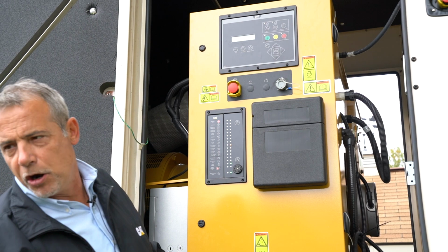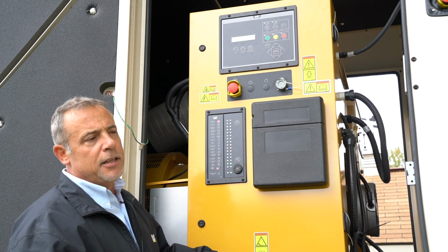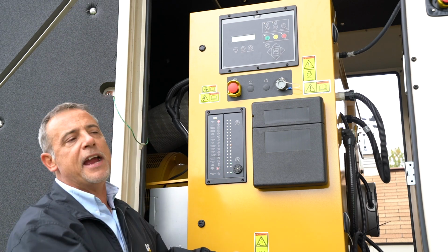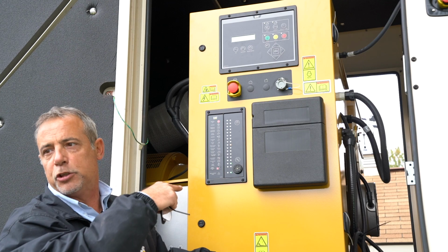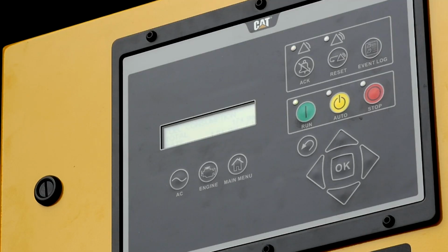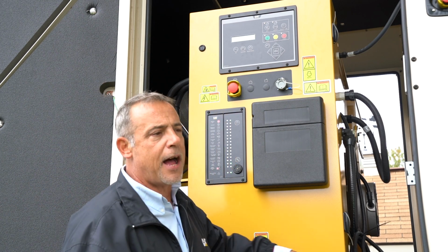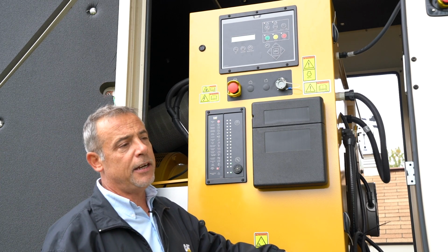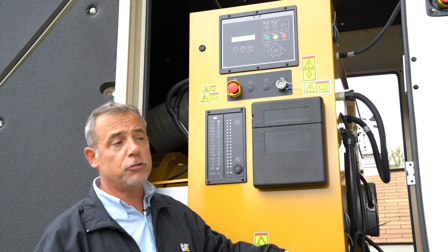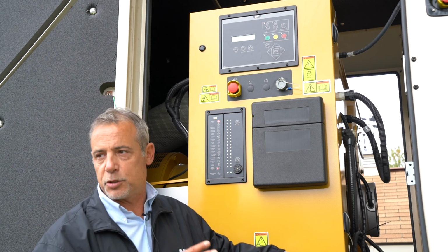Right now, we're burning 1.8 gallons. That's just in case the transfer switch doesn't start it, there's a break in the wire somewhere, you can come out here and push run. I tell people when they're stopping it, if you're manually running it out here, so you don't forget to put it back in auto, just push auto right away. It's going to shut it down unless the transfer switch is asking for it.